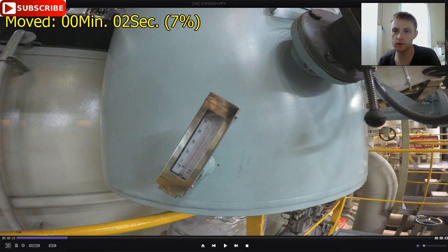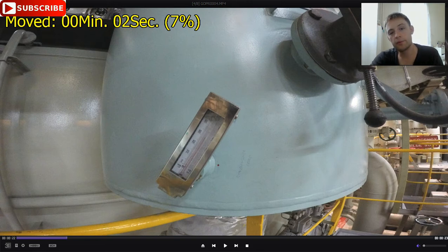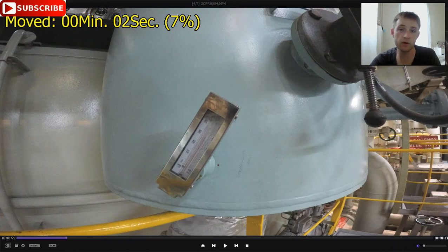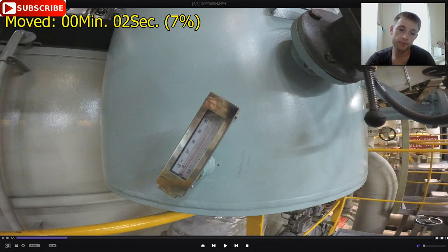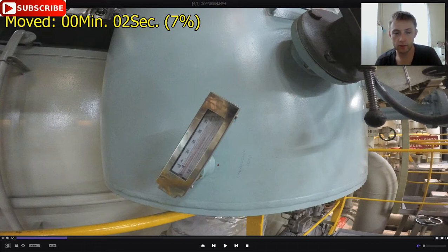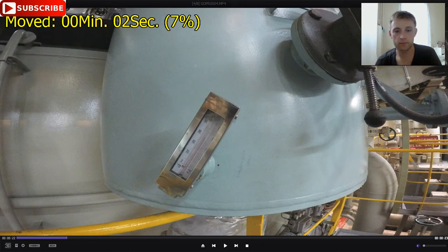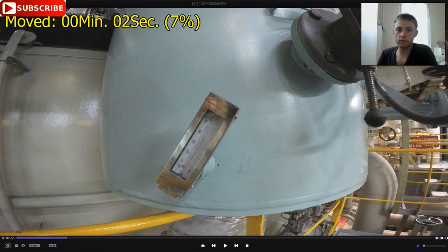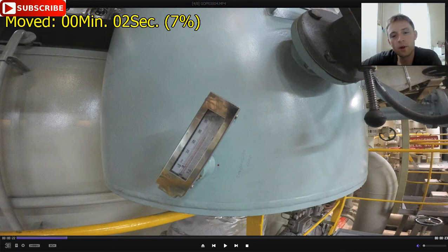60 degrees is okay for the condenser. Higher temperature will be closer to the boiling point of water. If you use about 80 degrees it will be more closer to the boiling point. In the suction of the pump there is lower pressure — sometimes coming to vacuum — and the boiling temperature will be lower, as we know from physics. This will be something bad for the pump because there will be development of cavitation in the pump casing and pump impeller, which we need to avoid.